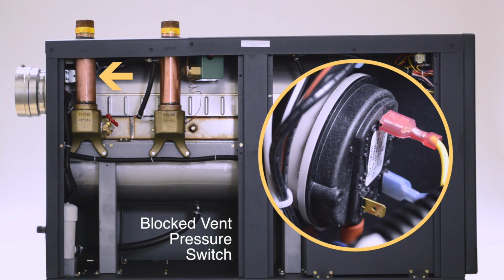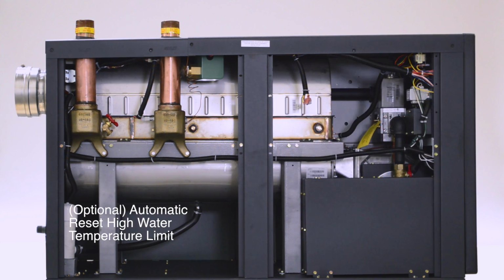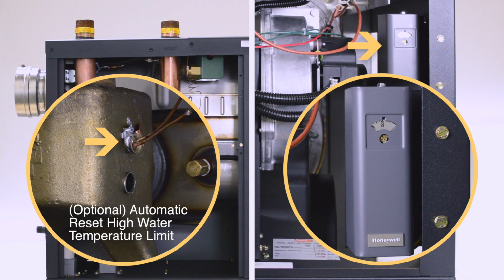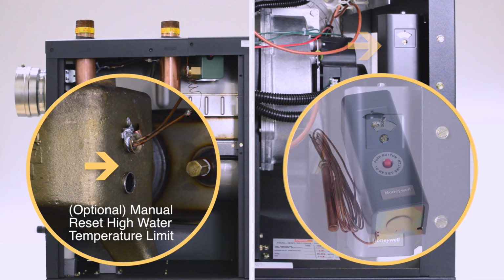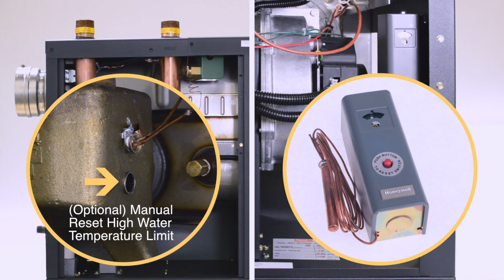A blocked vent pressure switch is standard. This shuts the unit down if the vent pressure rises to a level indicating that the flue gases cannot discharge to the atmosphere. Your unit may have an optional automatic reset high water temperature limit. If the temperature exceeds the limit, it will shut down the unit. When the system temperature drops below set point, it will reset automatically. Optional manual reset high water temperature limit. Must be manually reset if the temperature exceeds limit.